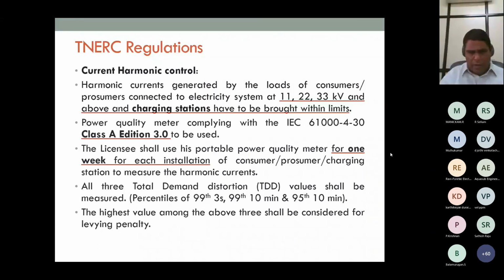You can run your industry as smoothly as possible with whatever load you are running. It is sufficient because the values are divided by IL, which is the maximum load current recorded over a period of 12 months. So in the regulations, the denominator is IL, and the numerator will be the THD values. So there will not be any issues. You can run the industries normally for a whole week, and there will not be any issues on the penalty side, or measurement issues that may crop up. So all these values have to be measured. The highest among them will be taken for levying penalty.